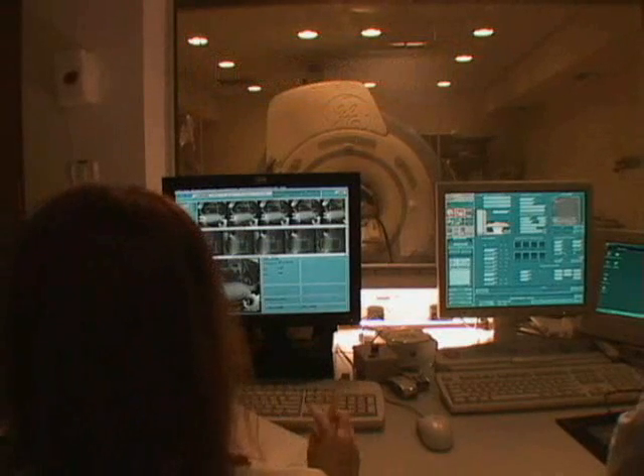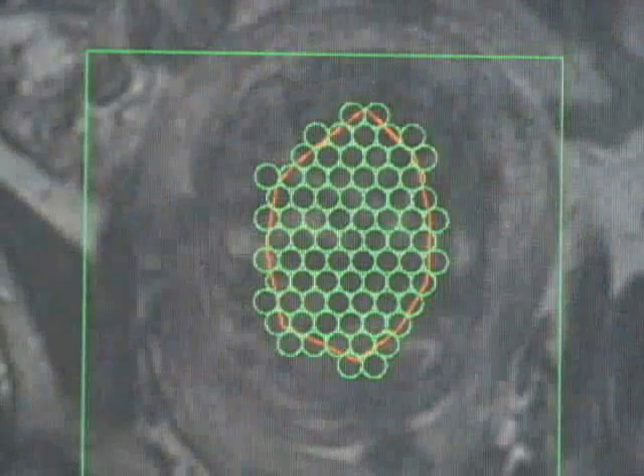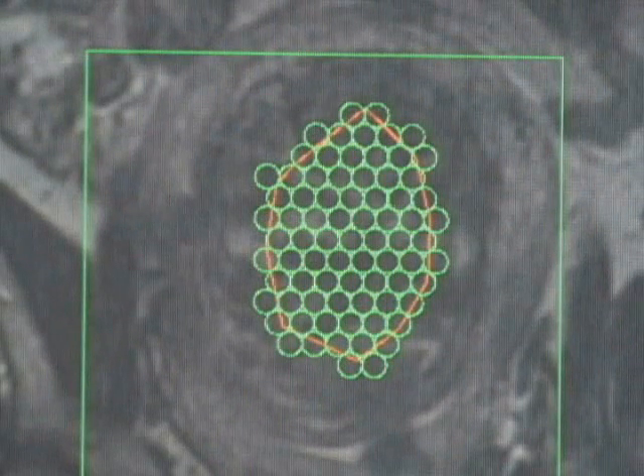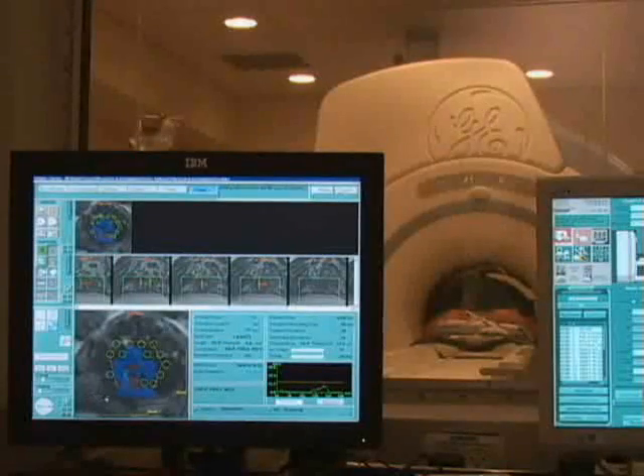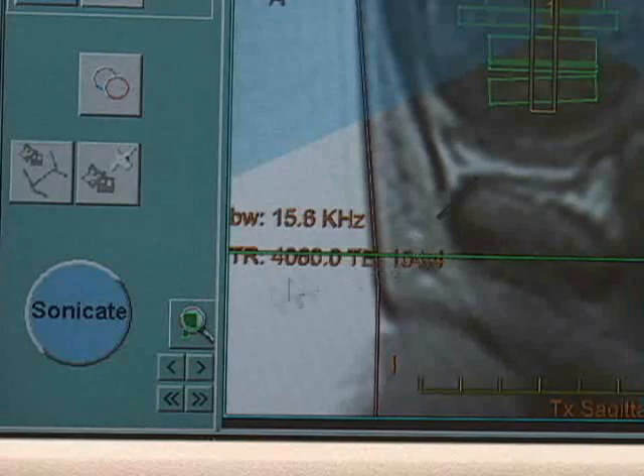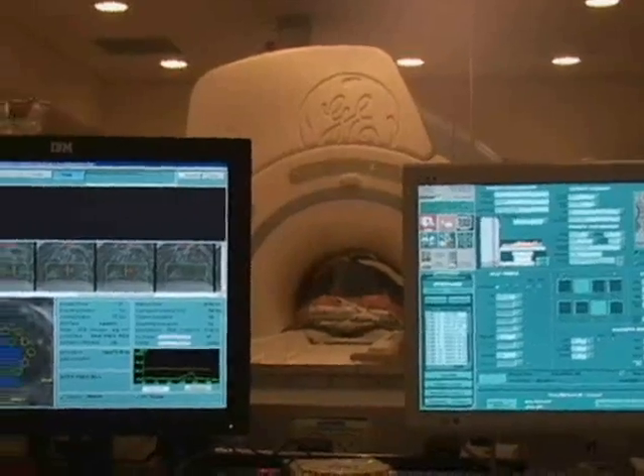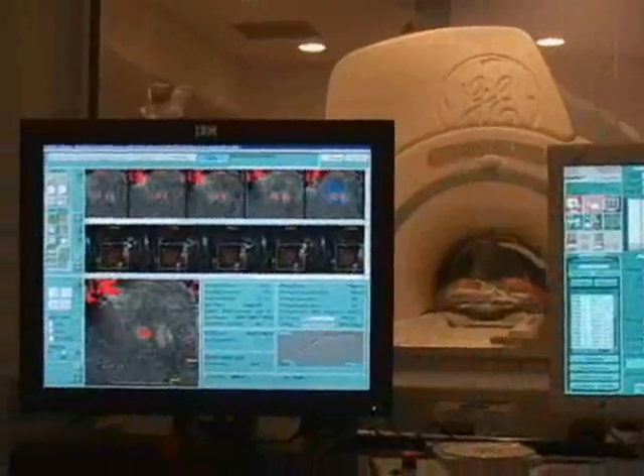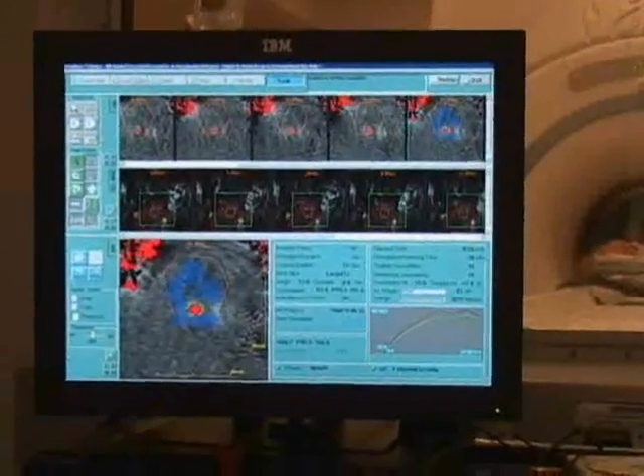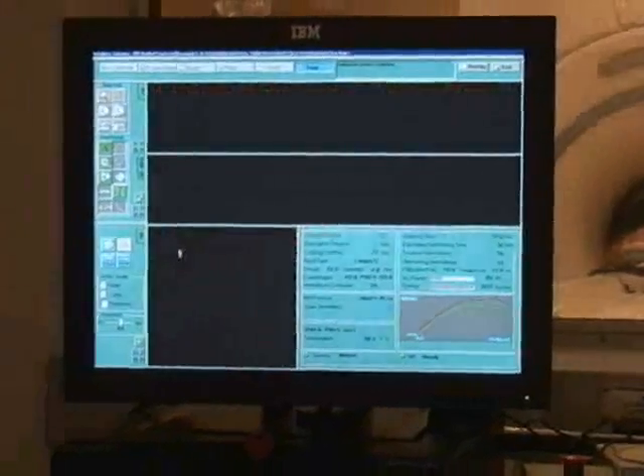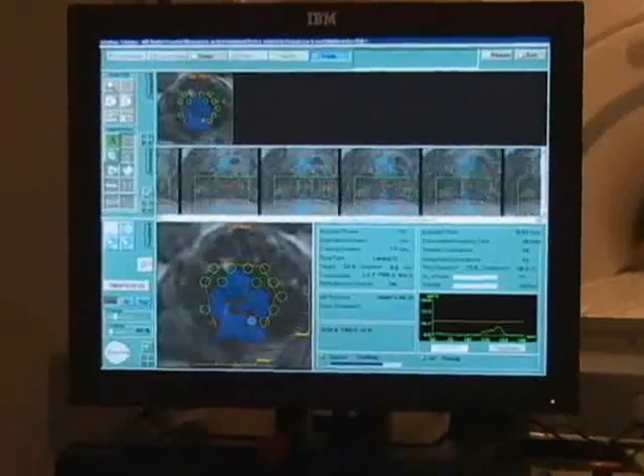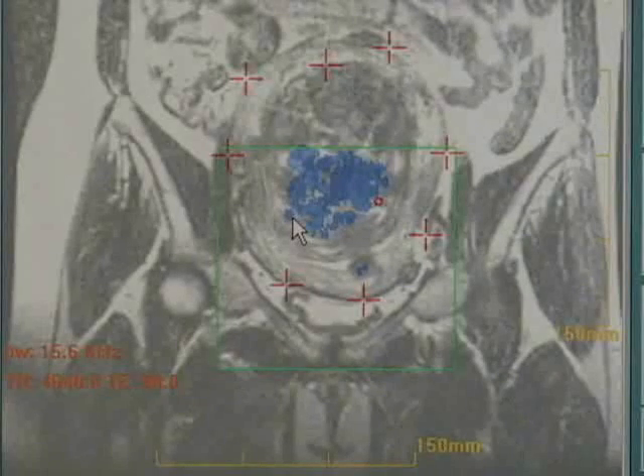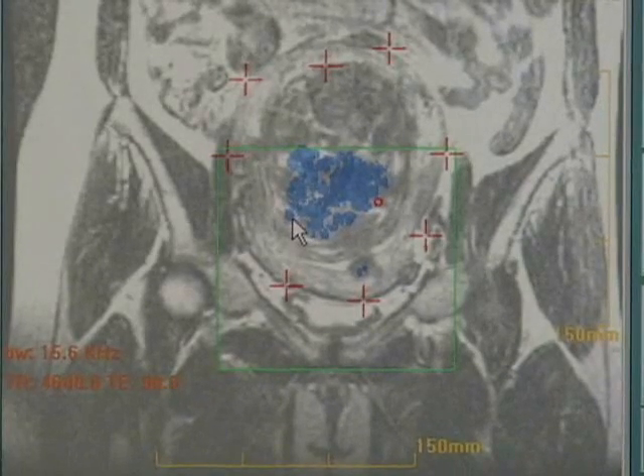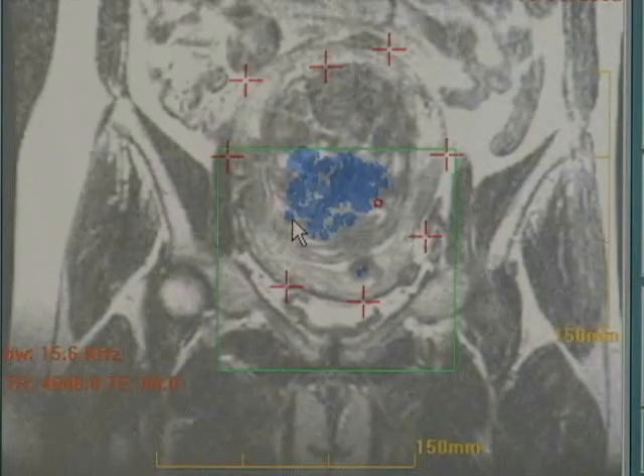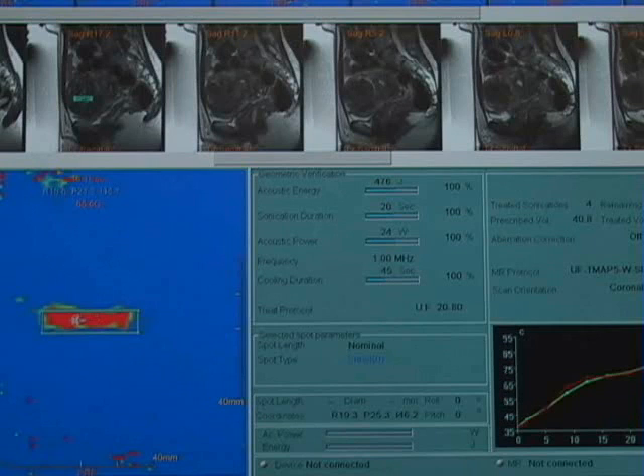Exablate treatment consists of multiple sonications, delivered in a planned grid until the entire tissue volume is treated. Each sonication lasts about 20 seconds with a scaled cool-down time. When the sonicate button is pressed, the MR begins scanning, energy delivery begins, and real-time thermal images and a temperature graph are displayed showing the temperature buildup. The physician knows immediately if the focused ultrasound energy has reached the planned spot and temperature. After each sonication, the ablated area is displayed in blue as accumulated dose. In addition, real-time anatomical magnitude images are shown to verify the location of the sonication.